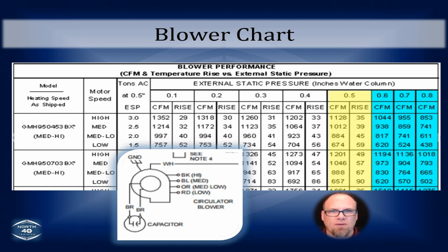Okay, once you figure out what those are for each fan speed, you go to that static resistance, go down the column, match it up with its corresponding CFM value, and set up your blower according to 400 CFM per ton for this manufacturer, and for most manufacturers, or 350 for just a few of them. But know what the manufacturer actually wants and set up that blower speed according to that.